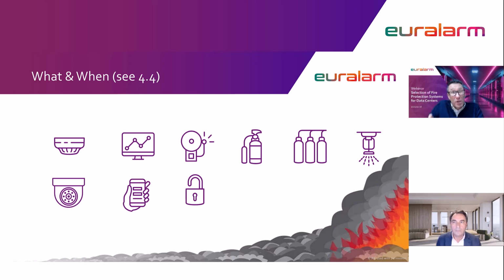And when we go to immersion tanks, that's a totally different beast, and that's where water mist would probably be better than a clean agent. But today, if you've got racks with air movement, I'm still very much a fan of inert gases doing their job, or a chemical agent. Then a sprinkler system is the last resort to safeguard the building, and it may be a requirement by the local authority or your insurer.